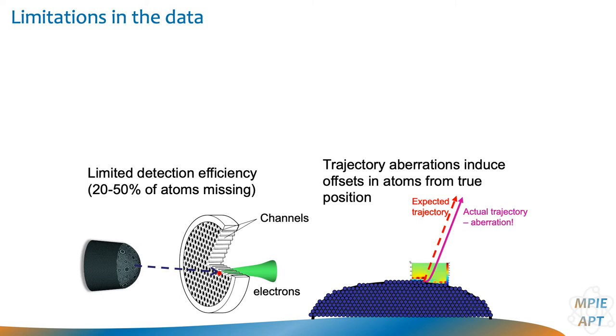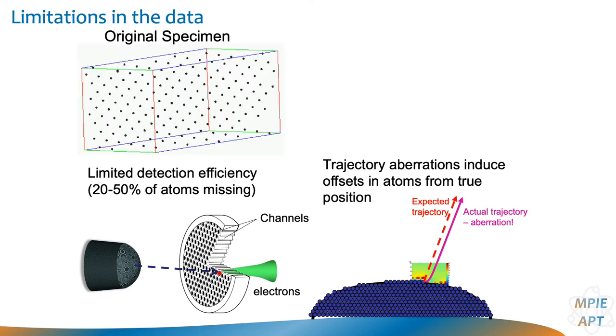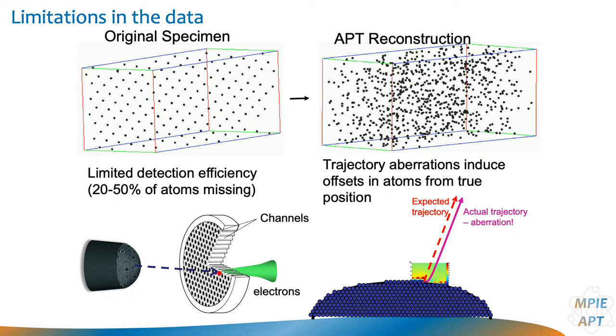We also have a limited detection efficiency — not all atoms are detected. This comes from the micro-channel plates at the entry face of the position-sensitive detector, which transform a single ion striking the detector into a cascade of about a million electrons collected by the anode, giving us positional information. So if we start with a nicely crystalline specimen, what we end up with in the reconstruction is a more amorphous-looking structure. But there is always the possibility to gain some crystallographic information from within this point cloud.